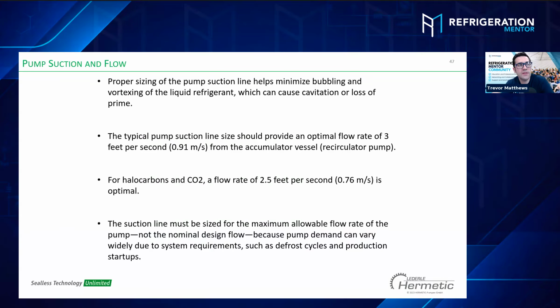So this wouldn't be, after the installation contractor puts it in, this would not be the installation contractor's job. This would actually be on the pump skid usually, because when I go to a store, I look at the refrigeration legend and it shows the flow rate. So it could be 270 gallons for the main. Yeah. So you're saying when someone designs a system, they're going to design it for all their loads, and they're going to say, our main, yes, needs 250 gallons. When they have it, it's correct.